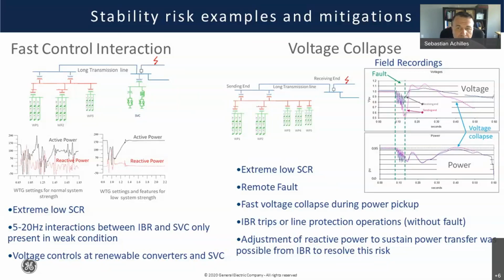The reason is that the speed of the voltage collapse is associated with the speed of the active power causing it. In this case, the active power injection from the IBR takes 200 milliseconds, and we see a voltage collapse in that time frame.